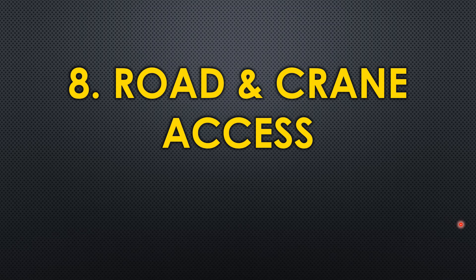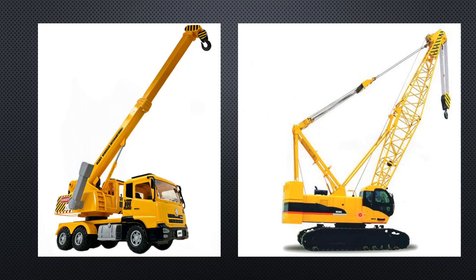The eighth parameter is road and crane access. Without crane and road access, you won't be able to install, remove, or maintain the pump. You must design the pump piping in a way that allows crane access. If you run piping densely over the top of the pump, the crane cannot reach it. Always provide maintenance accessibility for cranes to allow proper installation and maintenance operations.